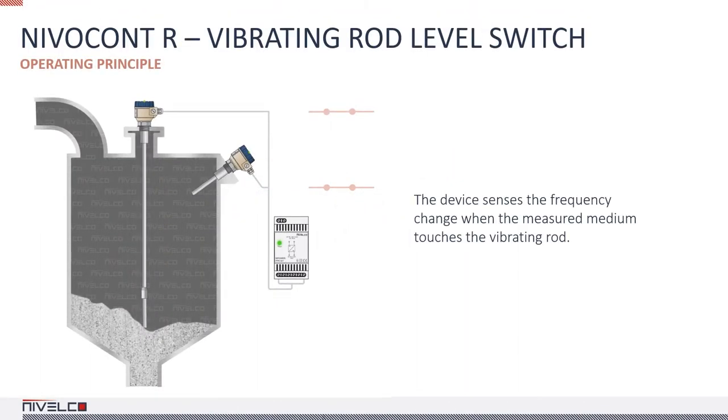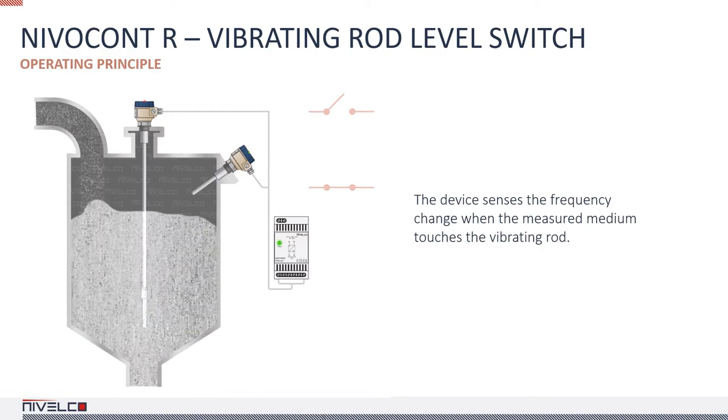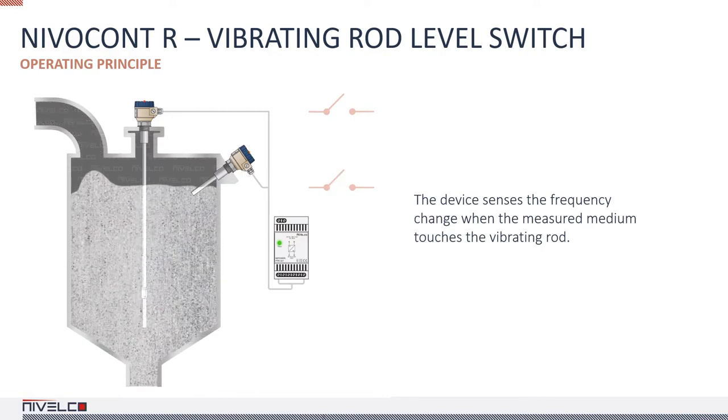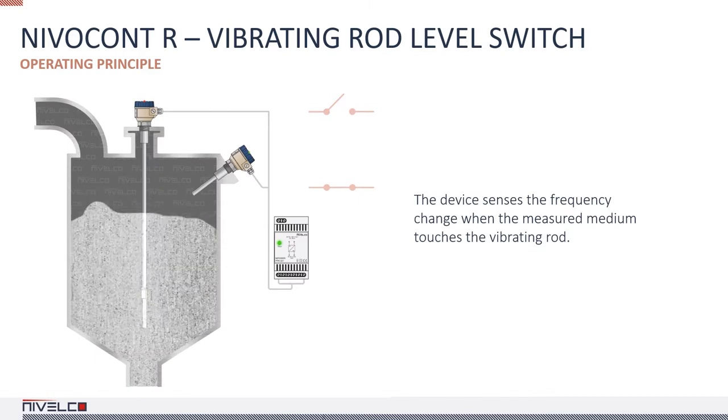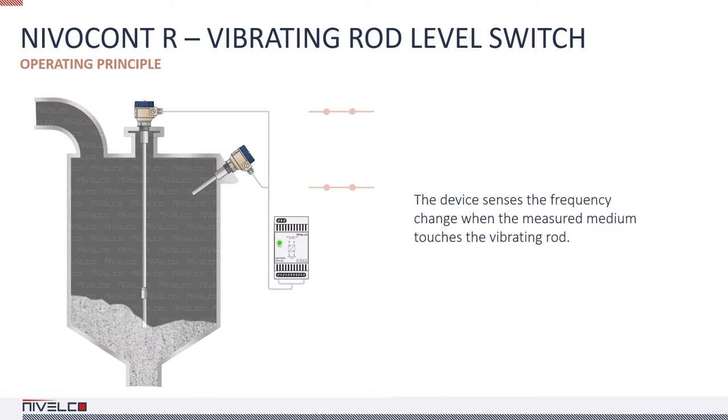The NIVOCONT R are vibrating rod level switches designed for high and low level indication of granules and powders with a minimum density of 0.0289 ounces per cubic inch. It controls the filling and emptying of tanks, silos, and hoppers, and it can send out an alarm signal when necessary.